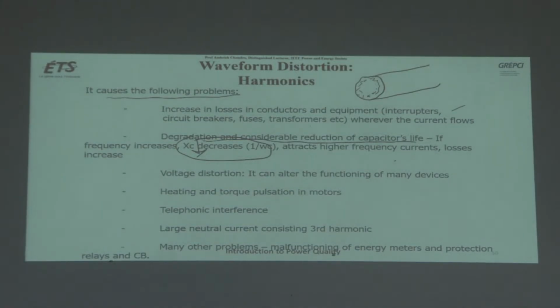Like I was telling you the example of the neighbor's load overloading the capacitor of another customer who did not have the non-linear load, but the harmonic current generated by another customer was attracted to the other capacitor nearby, and it was overloading and heating it, and it may decrease the life expectancy. Voltage distortion may alter the functioning of many devices, because of the zero crossing and those things. Heating and torque pulsation in motors.